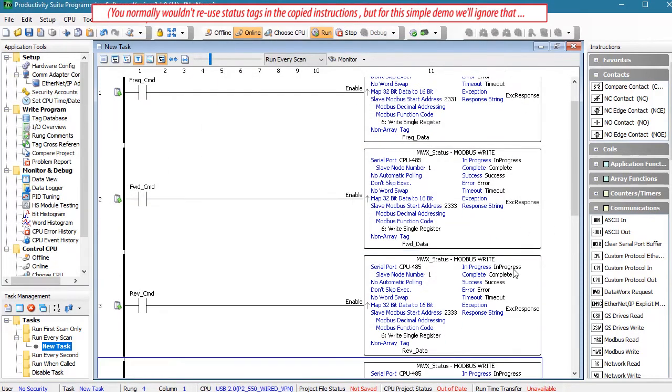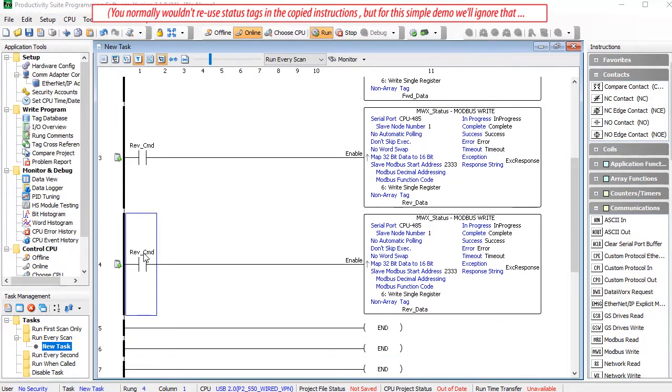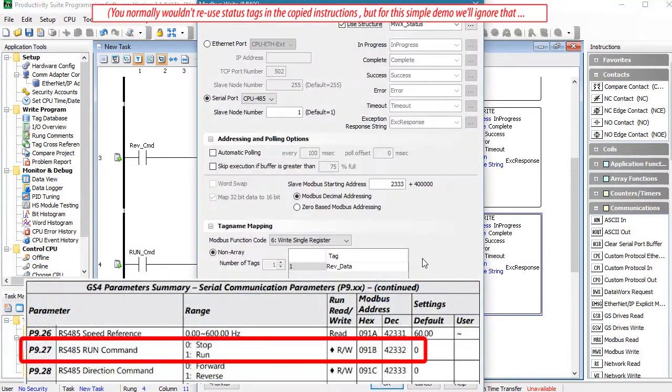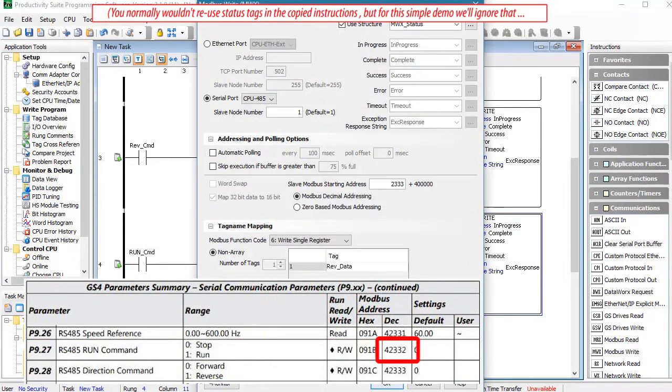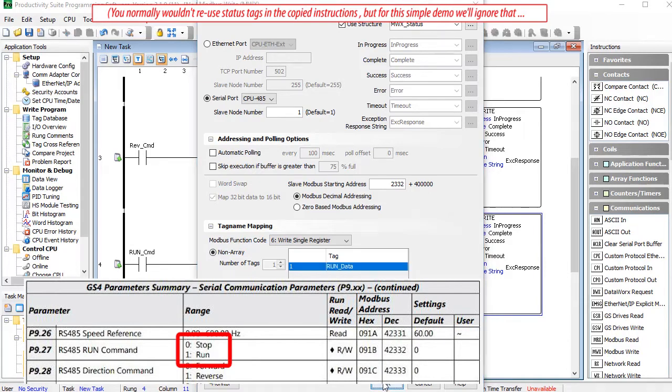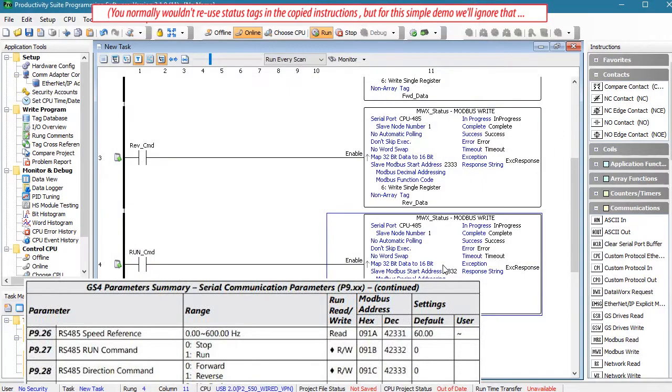Let's copy and paste that and create a run command. The RS485 run command is at address 2332 and let's create a tag to hold the run data, which again we'll set to a 1 in the data view.